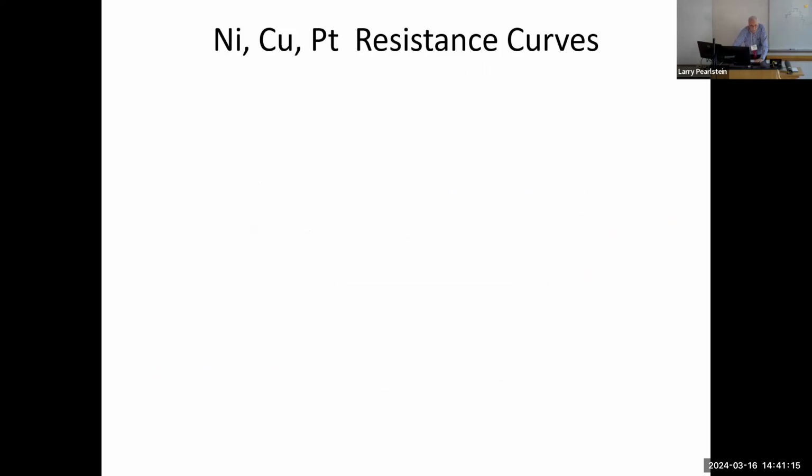Okay, well, basically it shows resistance curves of metals versus temperature. Characteristic of most metals is that their electrical resistance increases with rising temperature. It turns out that while platinum does not have the steepest curve, the highest temperature coefficient of resistance is extremely linear, which in the days before computer programs which could correct nonlinearities, it came to be the standard metal for thermometers.